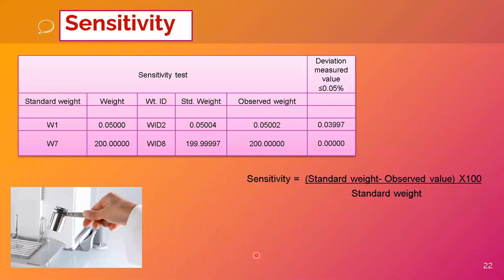Sensitivity is a very important test in performance qualification. Using our standard weights — W1 (0.05 g) and W7 (200 g) — we compare the certified weight value against the observed weight on the balance. Sensitivity = (standard weight − observed weight) × 100 ÷ standard weight. The deviation value must be less than 0.05% for the balance sensitivity test to be satisfactory.